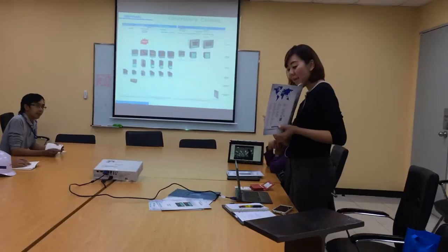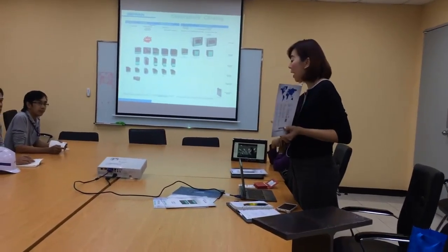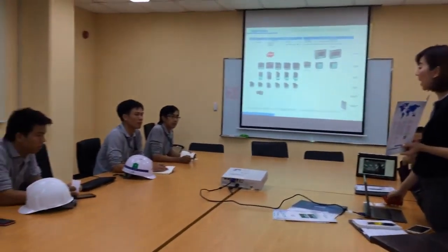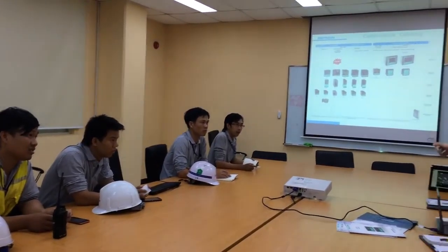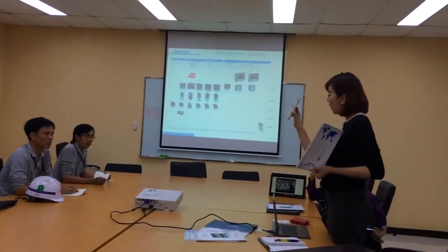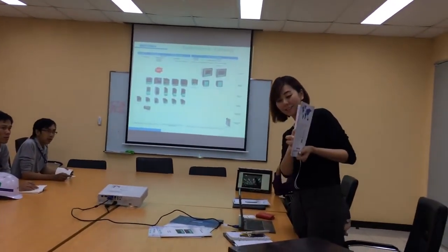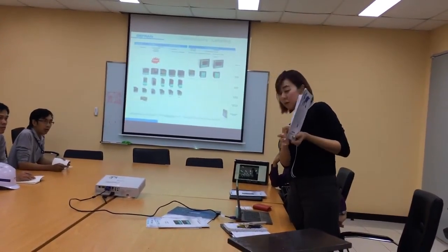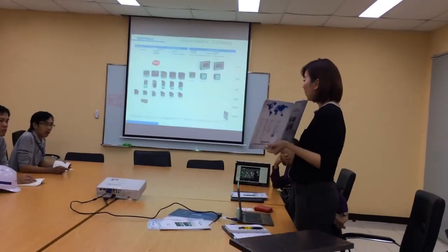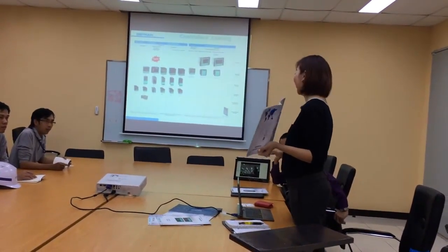Another thing is that we have this called a zapper. The zapper is slightly bigger, about the size of this phone, and it can store up to 4 recipes inside. You can put this small cable program to this zapper, and you can bring the zapper to your plant to copy and paste the program into the controller. Program to zapper, zapper to controller. Using the same cable, you connect the controller to the zapper, copy and paste, and you can go.